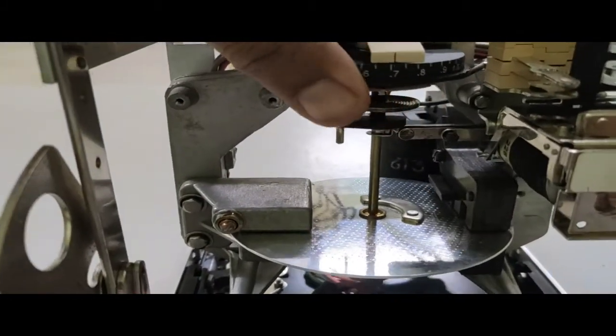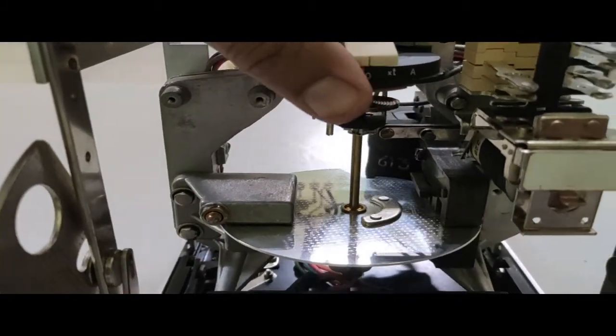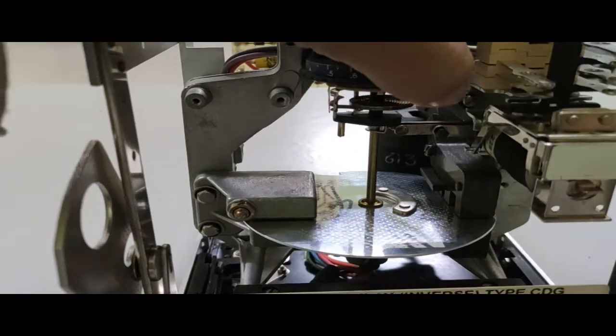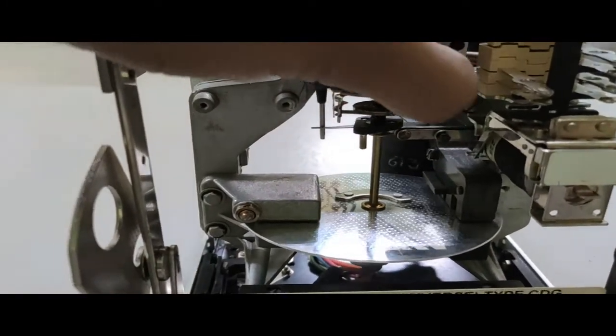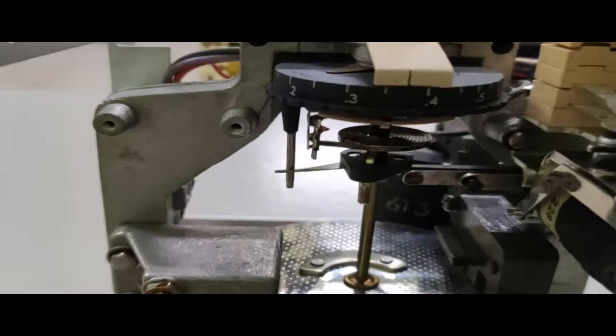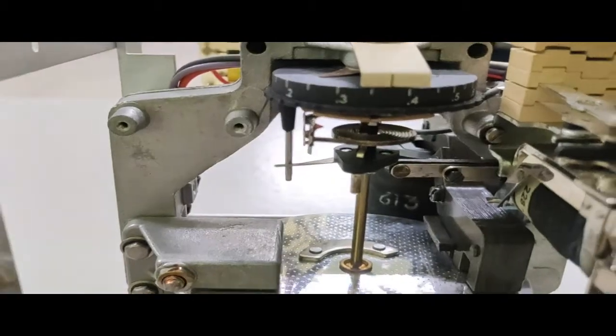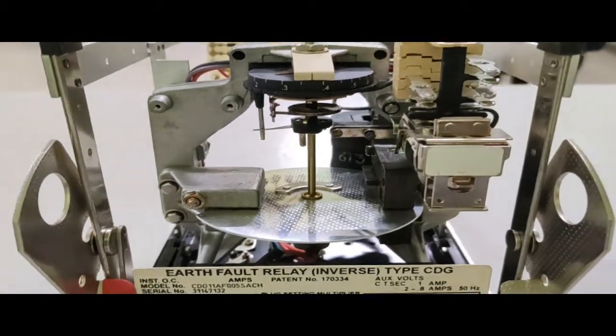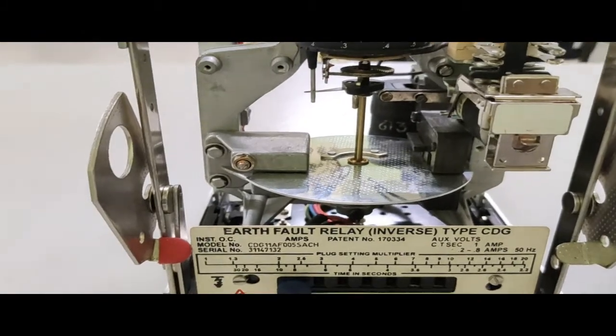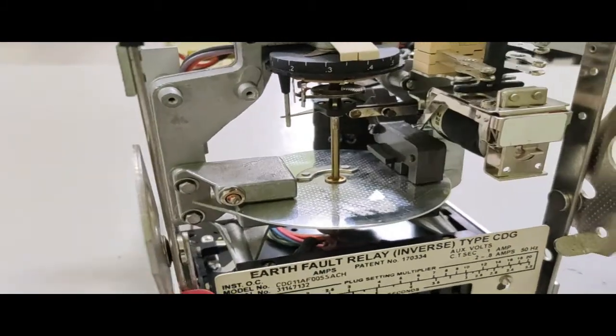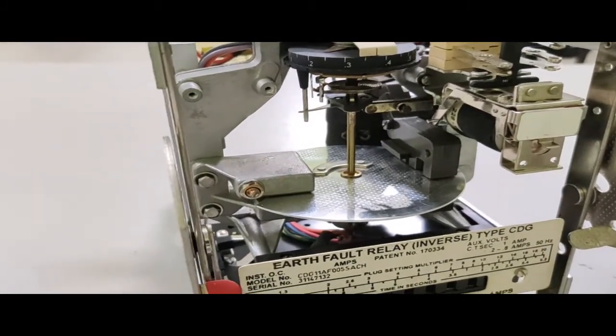Now here, apart from this one, you see another dial is there. This is called the time setting multiplier of the relay. Now what is the meaning of the time setting multiplier? Here you see that due to some reason we don't want an instantaneous relay. Intentionally some time delay is provided to the relay.